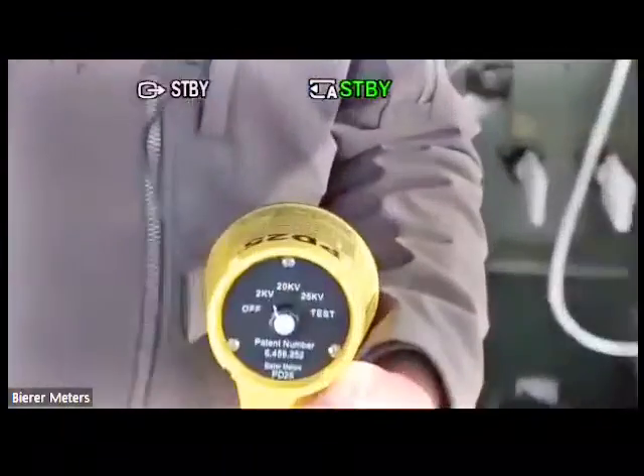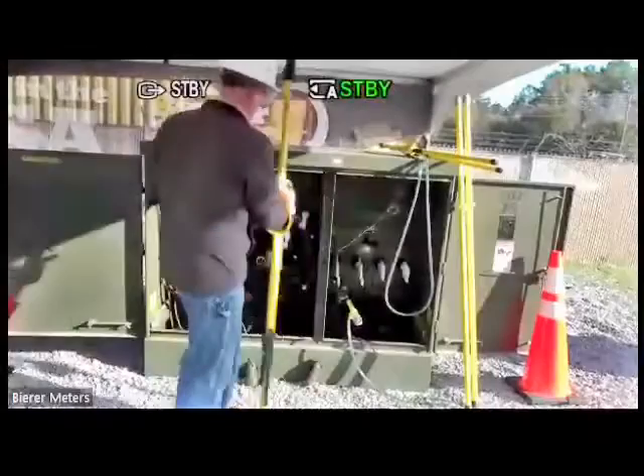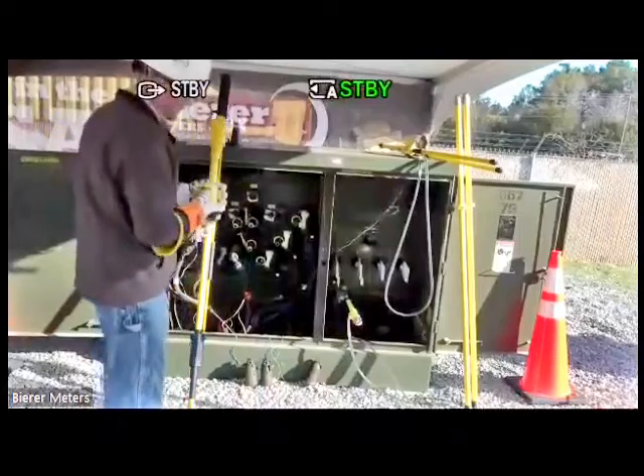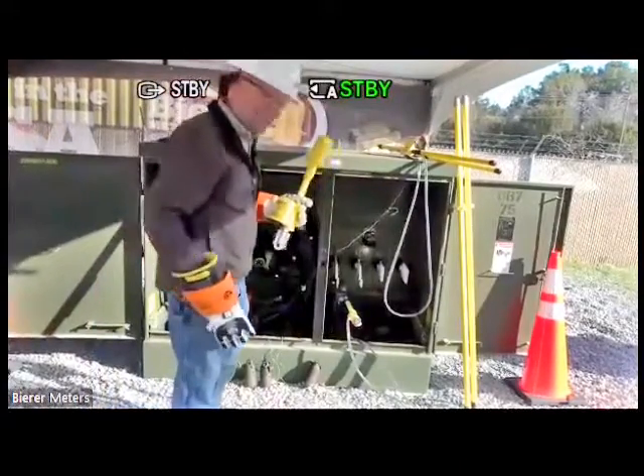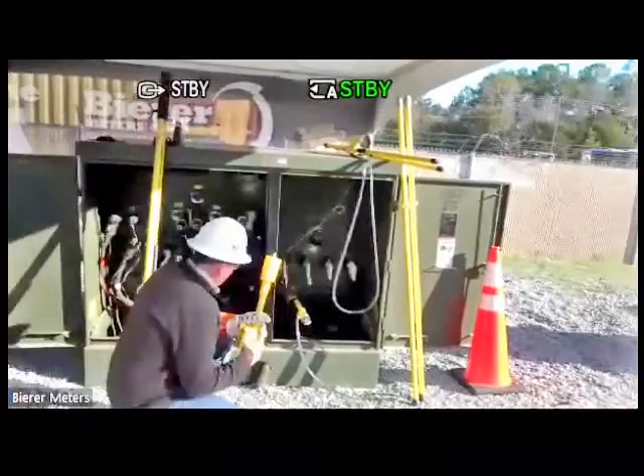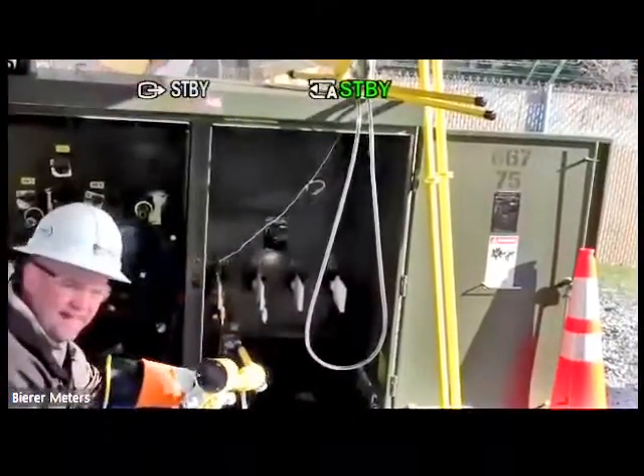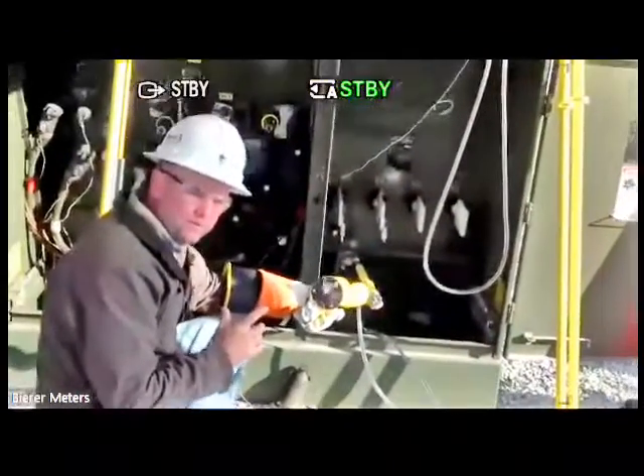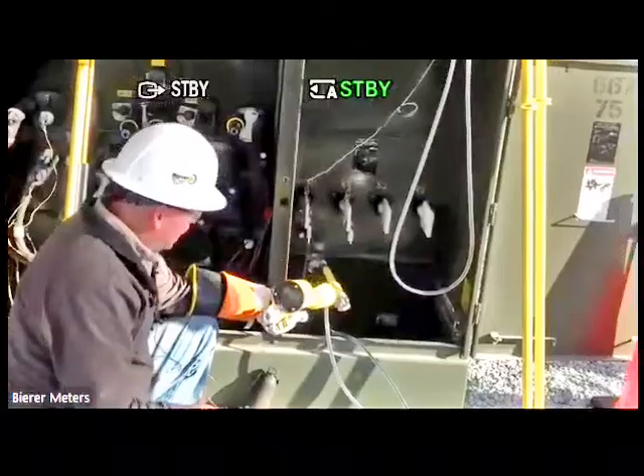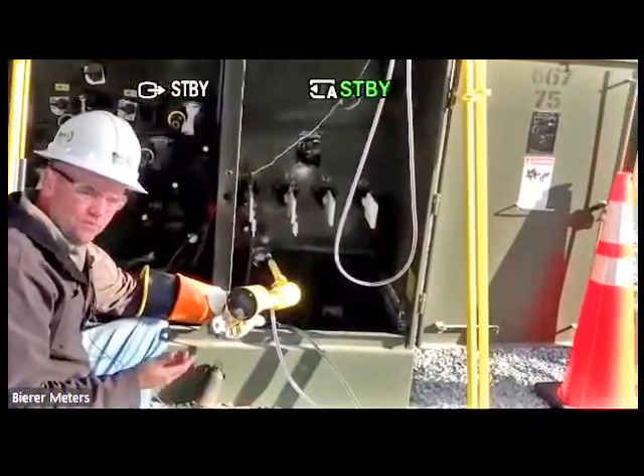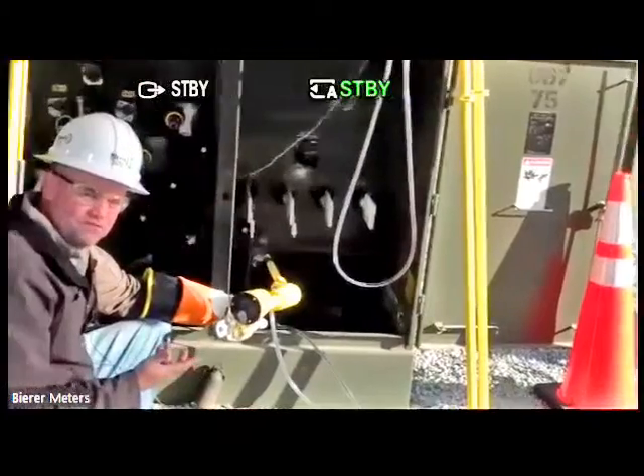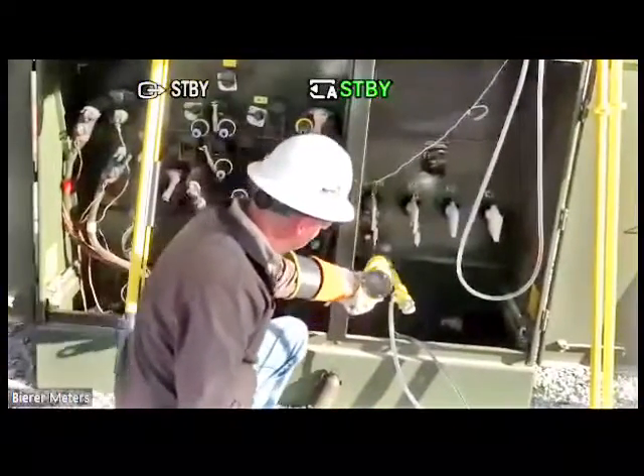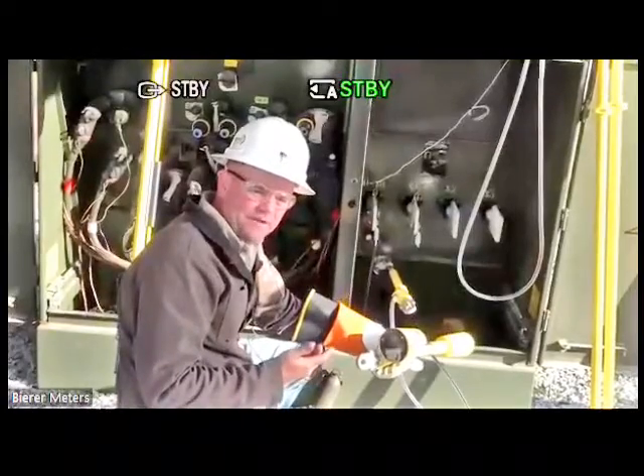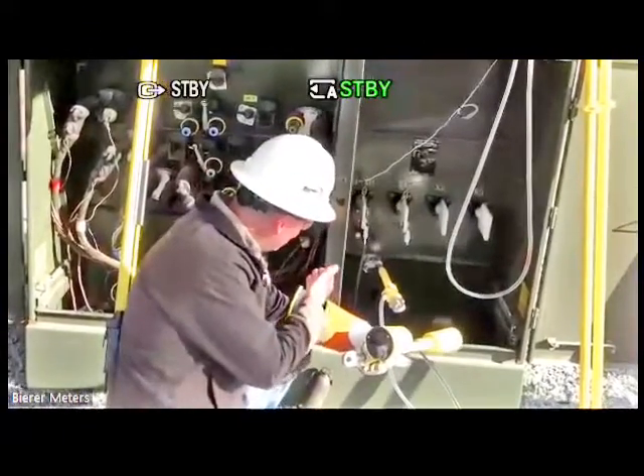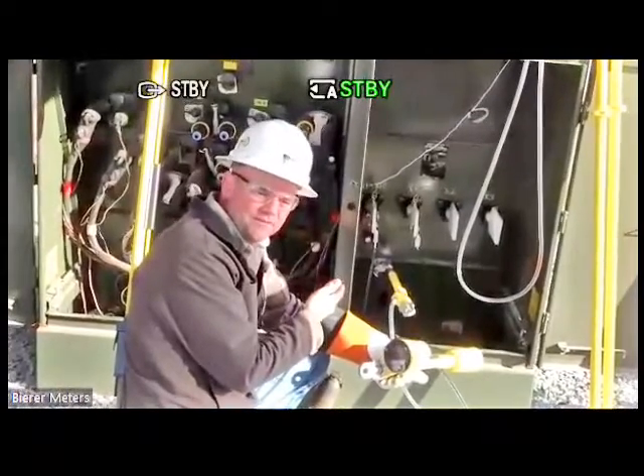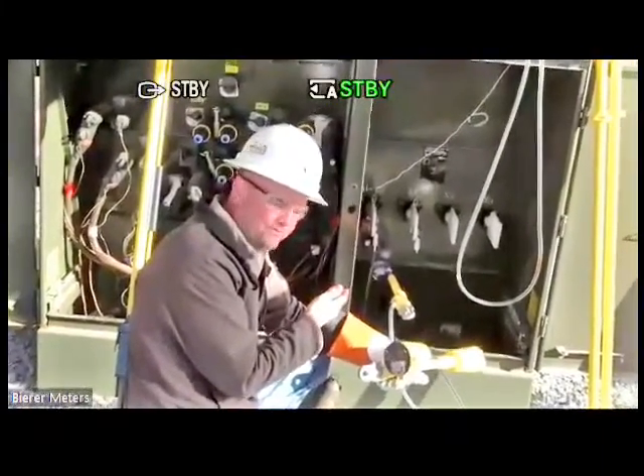Get Ryan to zoom in on the back. I'll just flip it in the 2 kV switch position. I'm going to get Ryan to zoom in on this real quick. And again, as I mentioned, there's one of two options to do this. I can connect another second probe to ground, and this is somewhat of a permanent fixture. A lot of utilities will order an accessory to the second probe, and they can attach any type of clamp that we manufacture to that. So I have one of our 3/4 C clamps adapted to the second probe to ground.